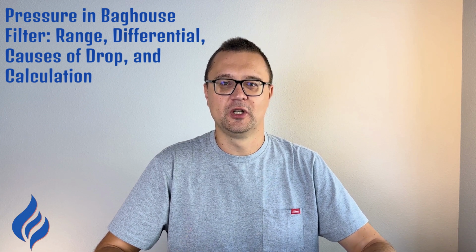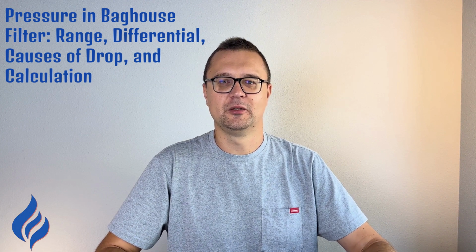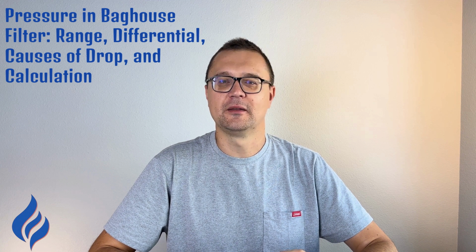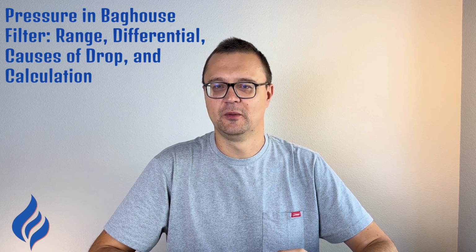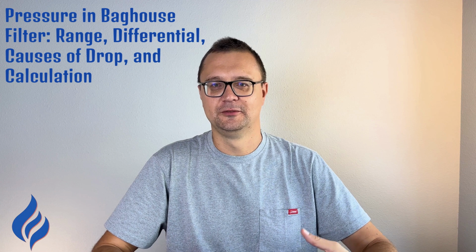Negative versus positive pressure systems. Now, there are two primary types of baghouse setups: negative pressure and positive pressure. Let's compare. Negative pressure: the fan is located after the baghouse, creating a vacuum that pulls air through the system, preventing leaks of polluted air. Used in many industries where controlling leakage is crucial, especially for hazardous dusts or fumes. Positive pressure: the fan is located before the baghouse, pushing air through. If there's a leak, contaminated air escapes. Common in systems where long-distance airflow is needed, like some large-scale industrial plants.